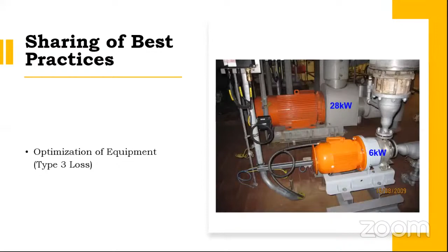So the equipment wasn't optimized. You could also install a variable frequency drive, but why would you install a VFD if your real solution in the first place is to replace it with a smaller sized motor? This happens a lot in plants—whatever is readily available, they just install it.